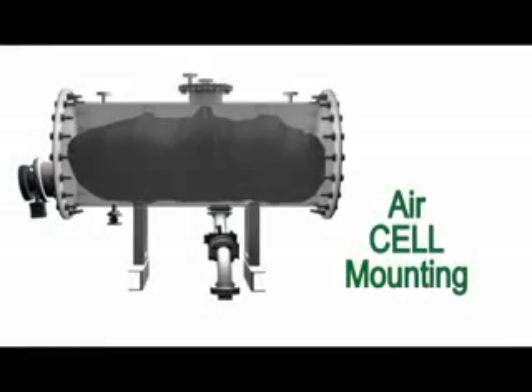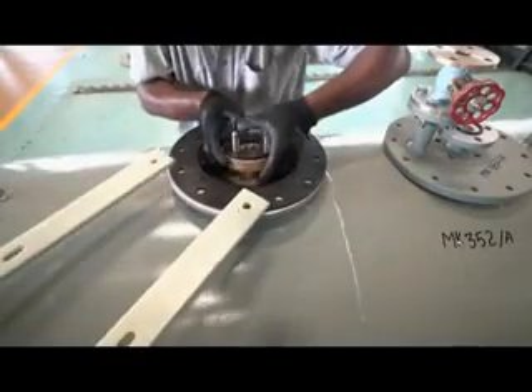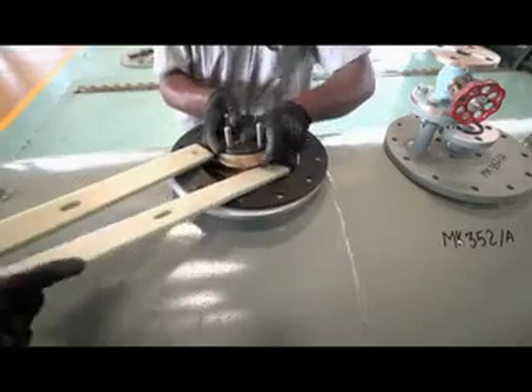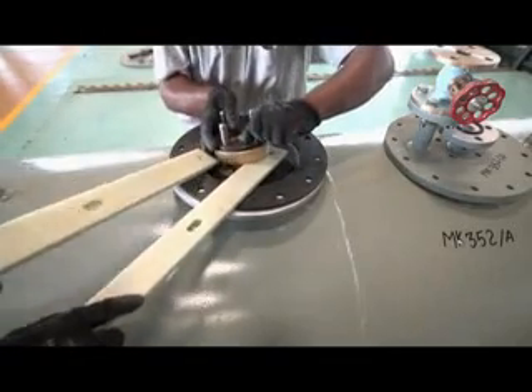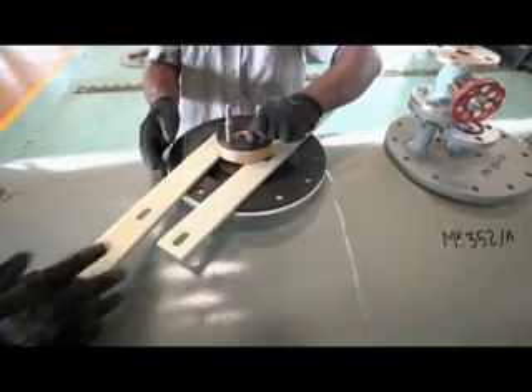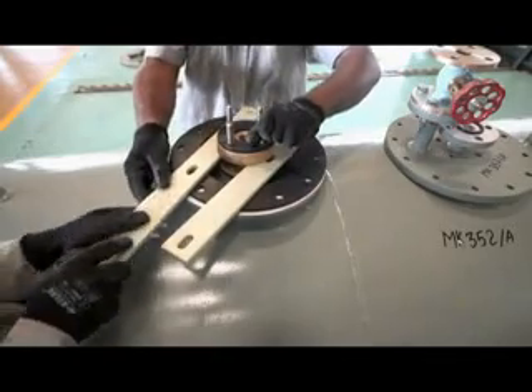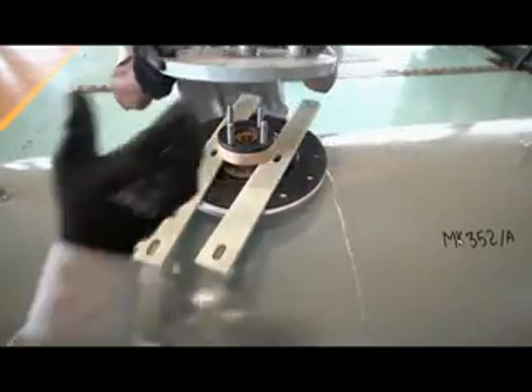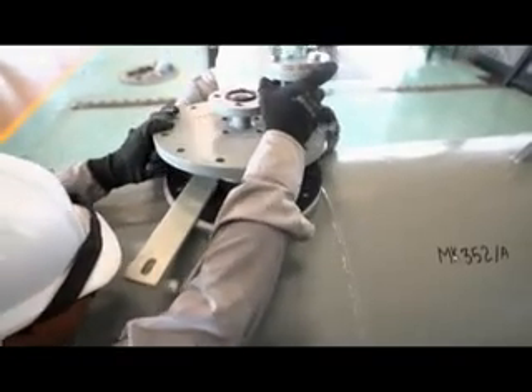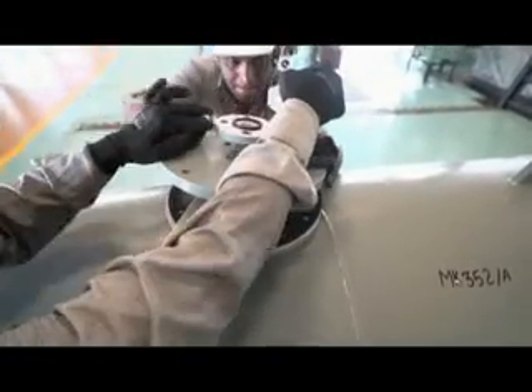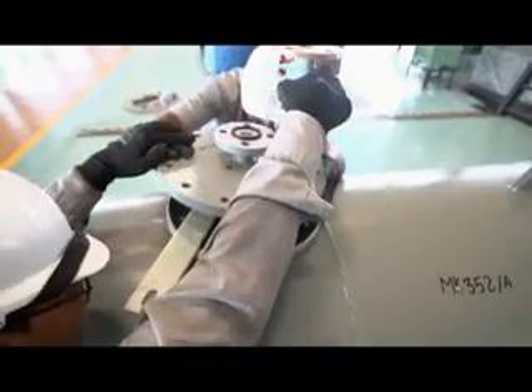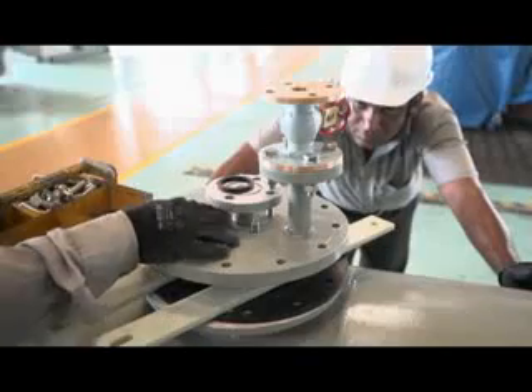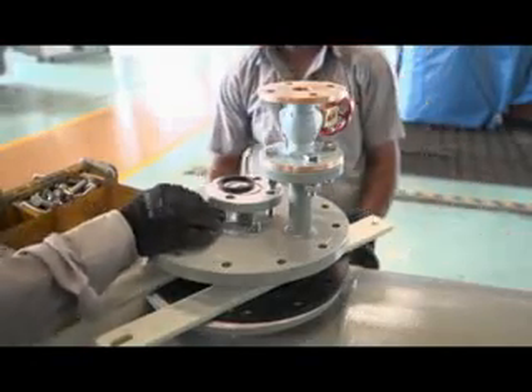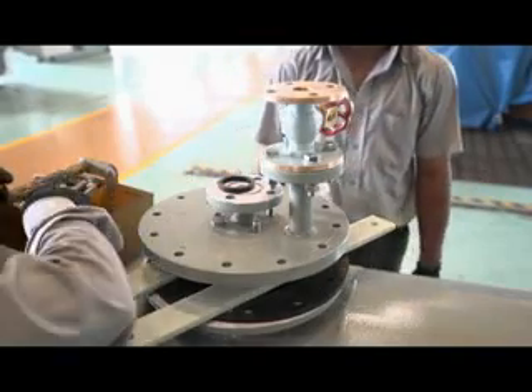Air cell fitting. The air cell flexible separator is fitted inside a conservator tank, isolating insulation oil from the atmosphere and thus preventing contamination of gas and/or moisture from coming in contact with the transformer oil due to oxidation and hydrolysis. The bag is vented on the transformer through flange type mounting such that it inflates or deflates to accommodate oil volume displacements due to change in the transformer temperature.